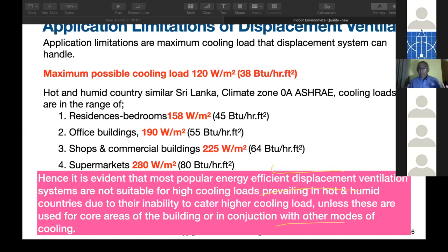Whether we can operate, because what I have seen, people simply get away from comfort and try all the juggling for energy conservation. No. Our prime aim in air conditioning is to maintain conditions: 55, 56 at least, 57 RH and 24 or 26 in balance. Suddenly, if the RH is 60 and temperature is 27, that is not comfort air conditioning. So high delta T, yes, please do it. But remember, not for constant air volume. ASHRAE says don't do that for constant air volume. And don't raise the temperature 13 and above from the return.